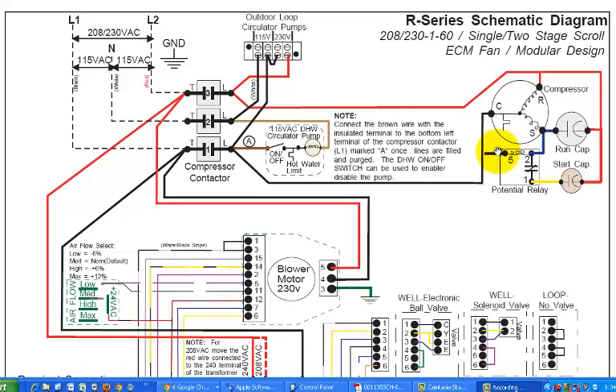Are we getting power where we're supposed to get power, and how is that operative, and how could we check it and see what's going on? So again, measuring these things with a voltmeter to see whether the power is getting to wherever it should be will give us a whole bunch of information. For example, if we were to measure voltage between this point and this point, because we always have to see two sides of voltage, and we've got 240 volts showing up there, but then we come across and measure to this point, and we don't have 240 volts showing up there, that narrows our problem down quite significantly. It's the compressor contactor, or it's something that is not actuating the compressor contactor the way it should be.